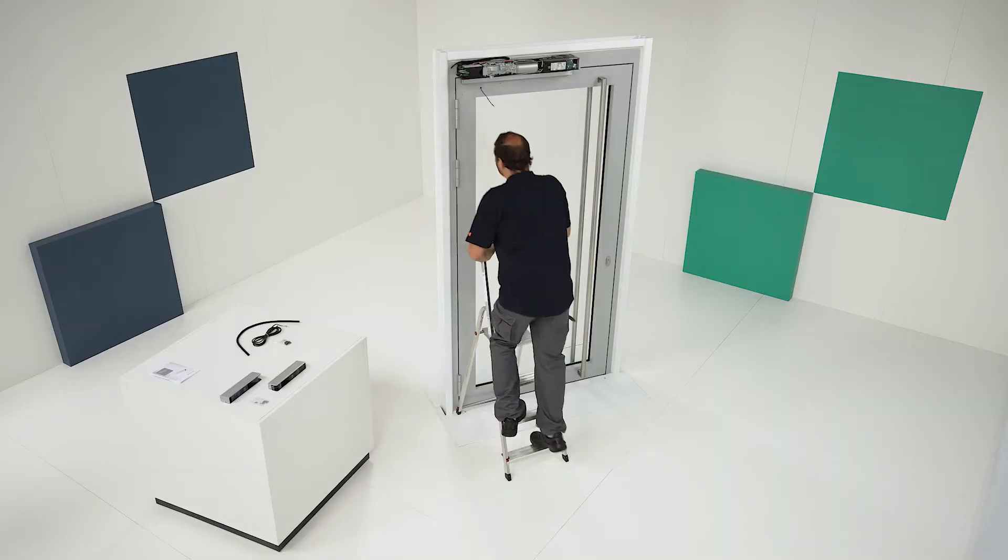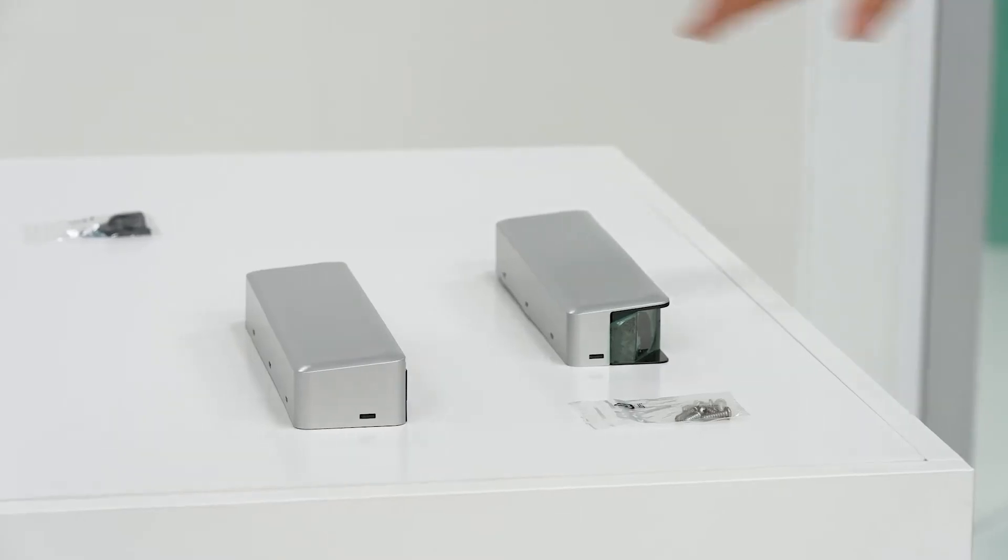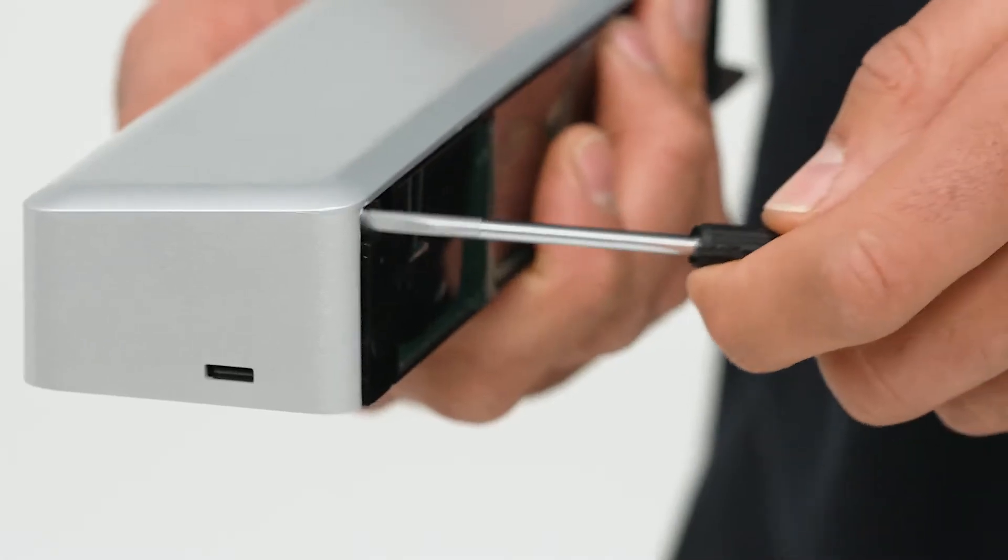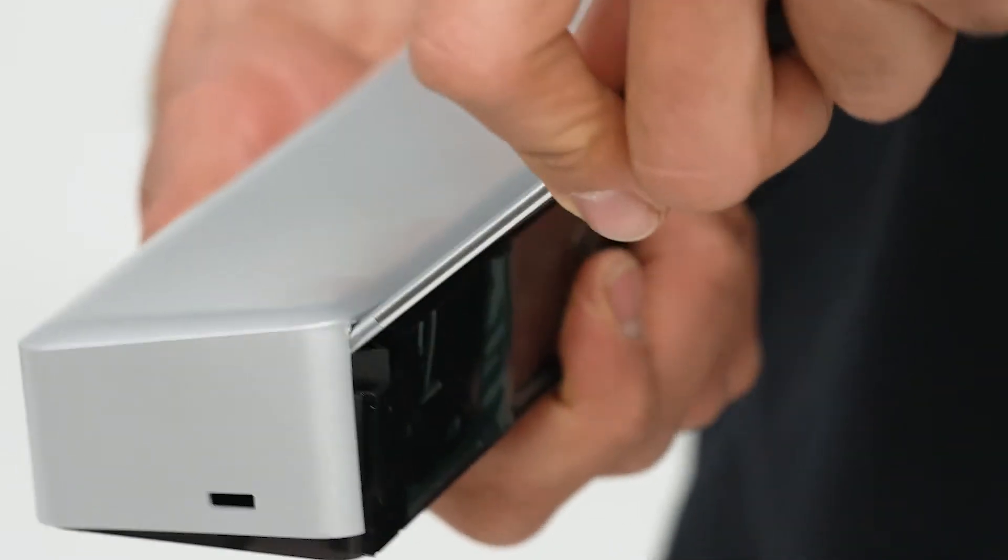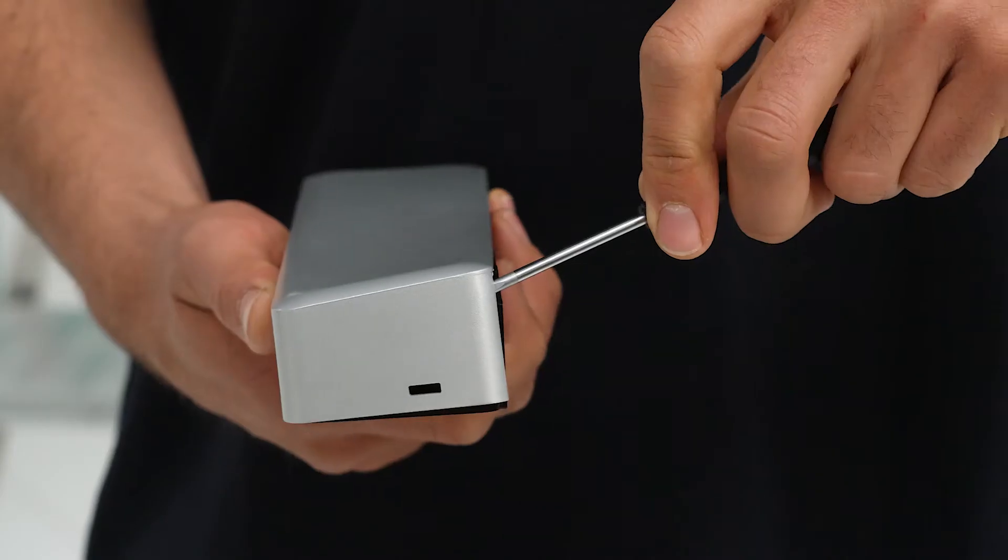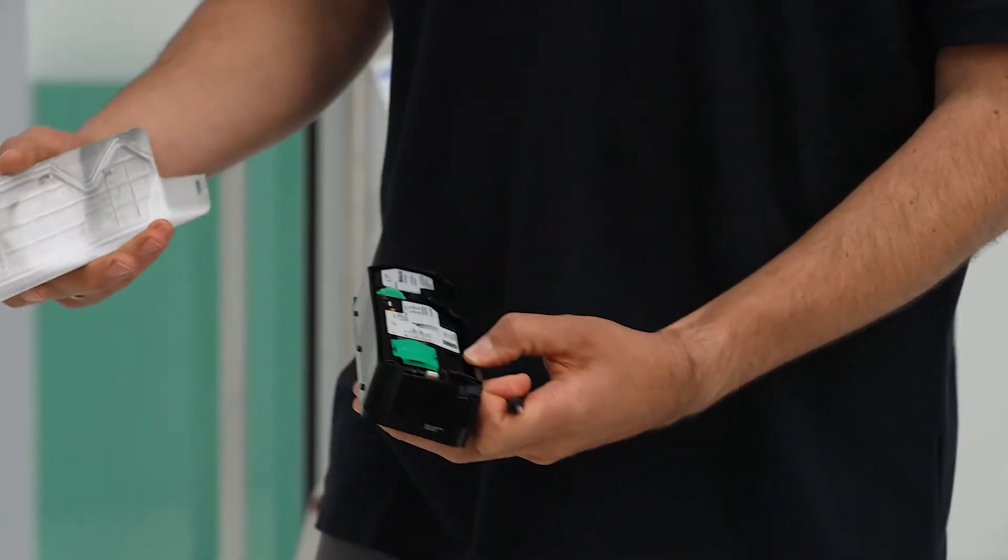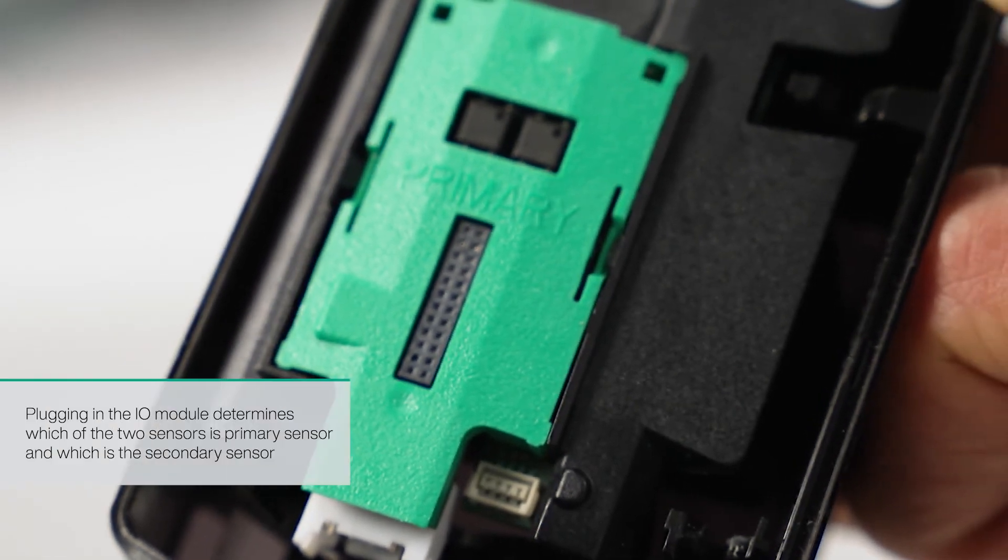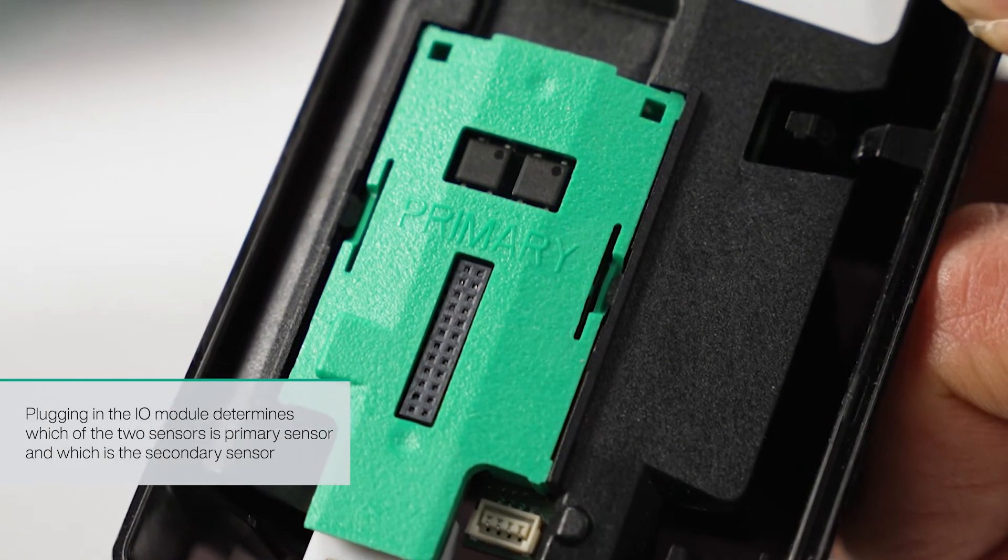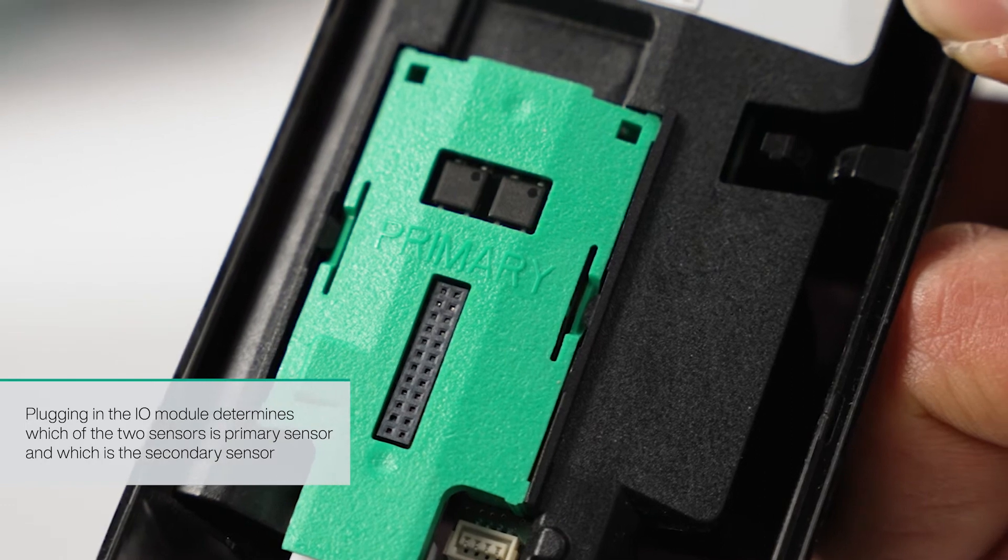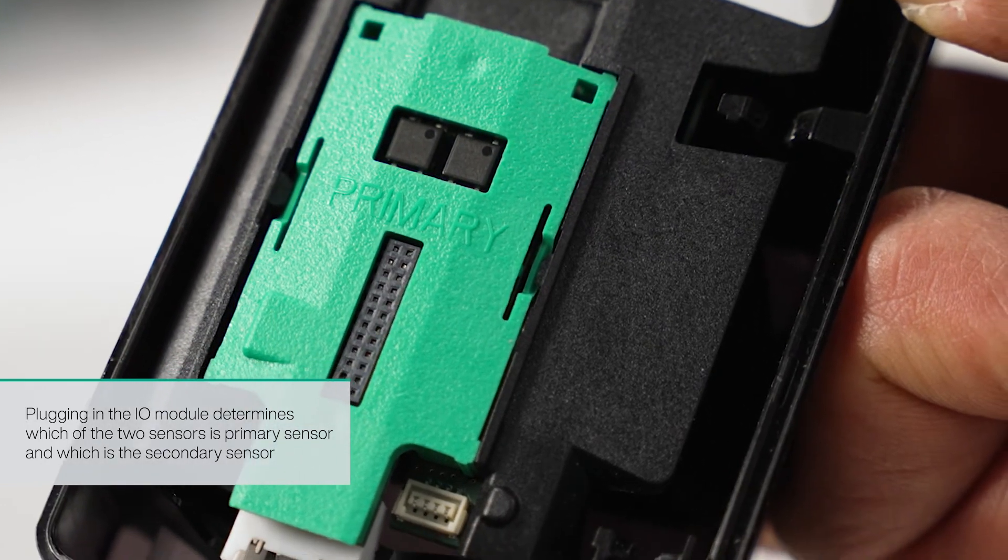Next, install the primary module on the drive side. To do this, remove the cover by inserting a screwdriver into the marked opening and pushing the side wall of the cover outward until the rear catch is released and the inside of the primary module becomes visible. The I.O. module connects to the primary sensor on the drive side. As the secondary sensor is not connected to the I.O. module, a blind cover is used here instead.